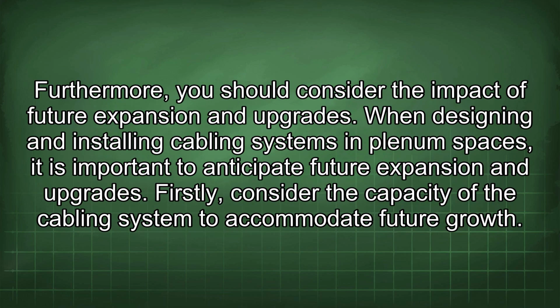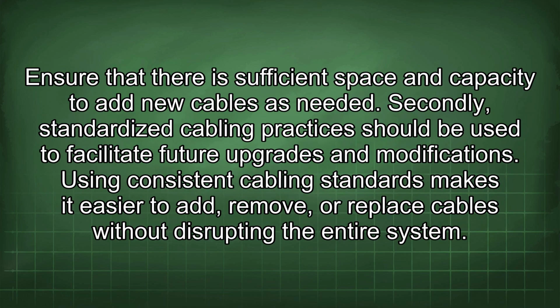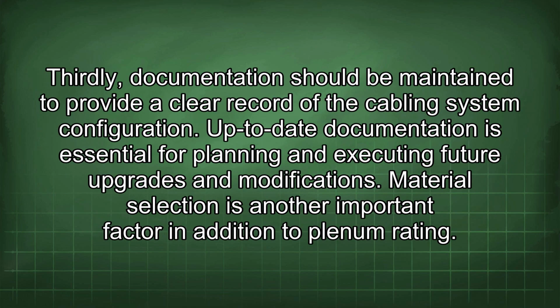Furthermore, you should consider the impact of future expansion and upgrades. When designing and installing cabling systems in plenum spaces, it is important to anticipate future expansion and upgrades. Firstly, consider the capacity of the cabling system to accommodate future growth. Ensure that there is sufficient space and capacity to add new cables as needed. Secondly, standardized cabling practices should be used to facilitate future upgrades and modifications. Using consistent cabling standards makes it easier to add, remove, or replace cables without disrupting the entire system. Thirdly, documentation should be maintained to provide a clear record of the cabling system configuration. Up-to-date documentation is essential for planning and executing future upgrades and modifications.